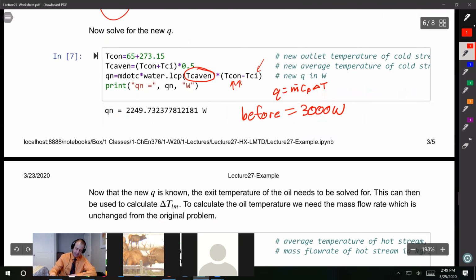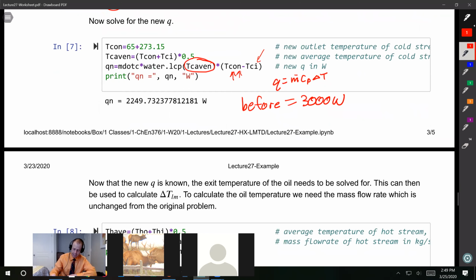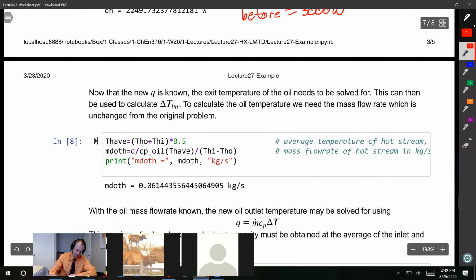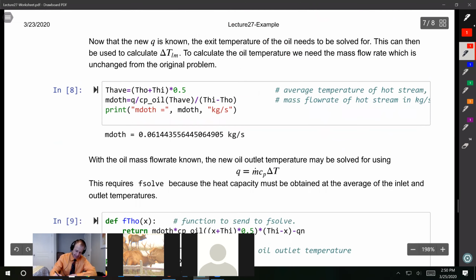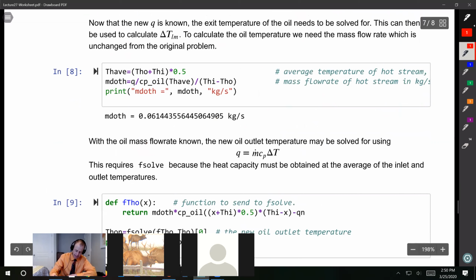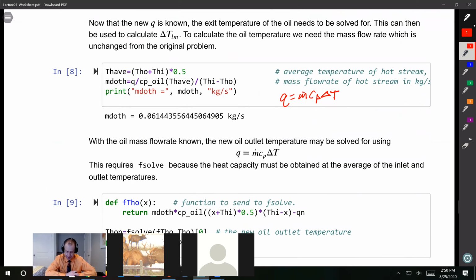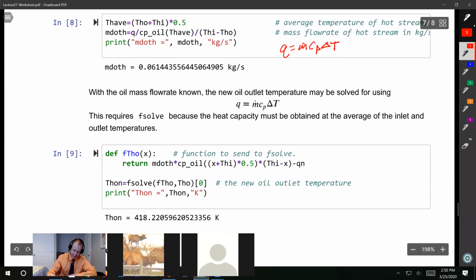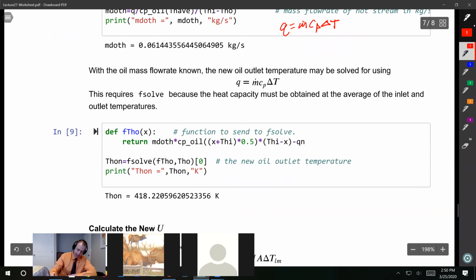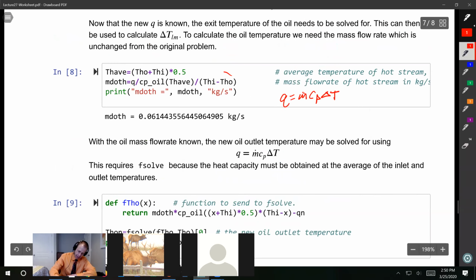How am I going to get my new U? Because that's how I'm going to get the fouling factor. I need to calculate m dot again for the hot stream, since I didn't have that. This is just m dot CP delta T, that's my m dot hot. The oil doesn't need to flow that much to heat it up because it has so much thermal mass. And this was with all my old stuff, my initial conditions.